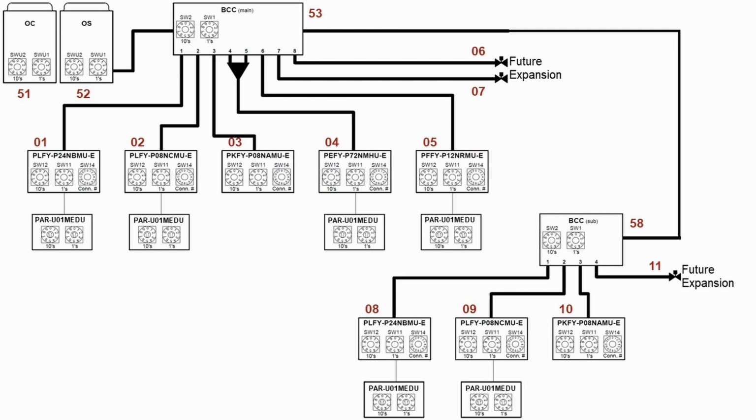Since ME controllers are connected to the network, they control by address, so they must be addressed. The ME controller should be addressed the same as the indoor unit that you're wanting to control. The 100 is pre-programmed in the logic of the controller. So if you're wanting to control address 01, you would set the ME controller at 01. It would be seen in the system as 101 to identify itself as an ME controller.